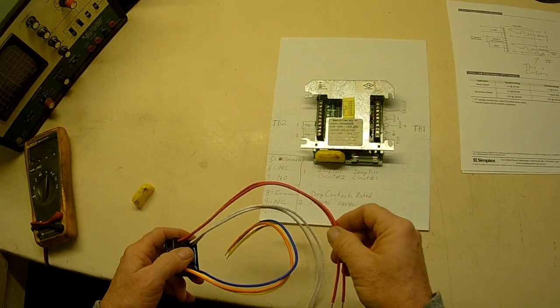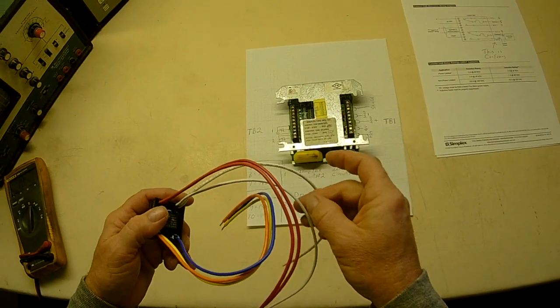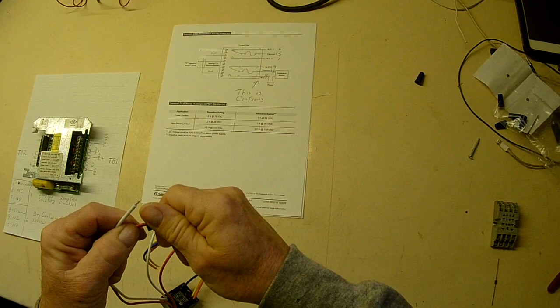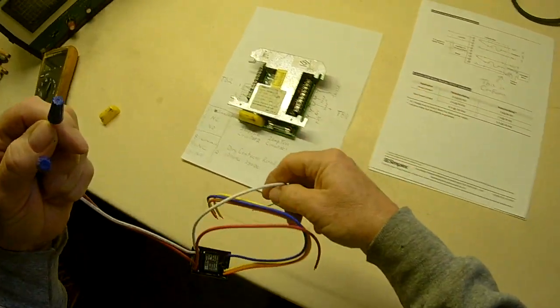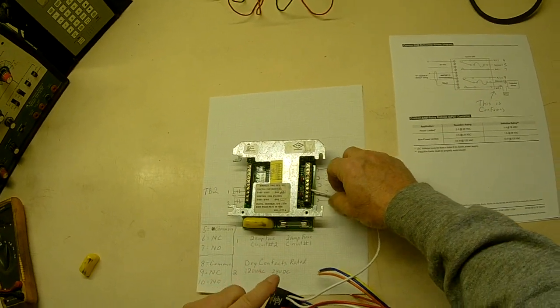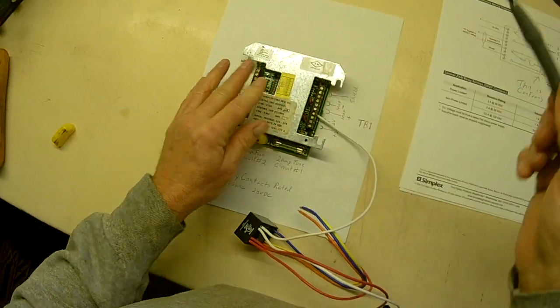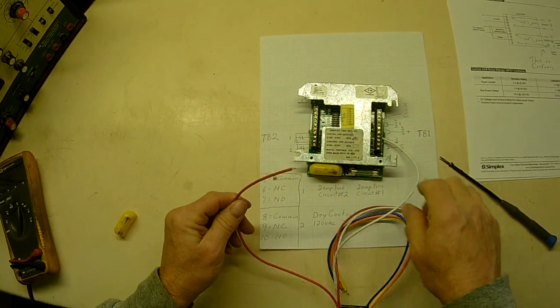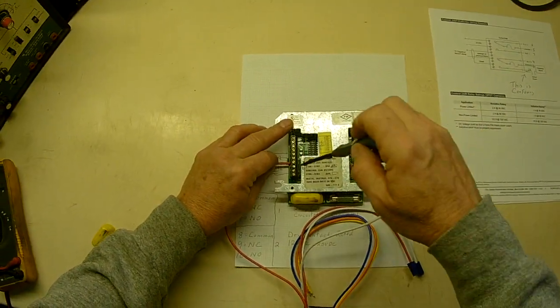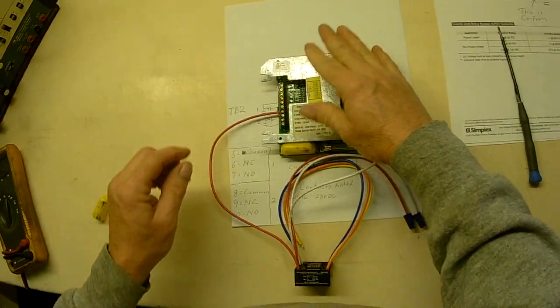So I guess in this situation here, what we're going to do on this is we'll go ahead and take, let's go ahead and take our white wire, one white and red, one red. We're not going to use, we're going to get rid of that. So let's go ahead and say goodbye to a red and white for the time being. White is negative, so we'll go over here to negative and we'll go on zero volts. We're assuming that there's already a negative wire on three. And then we'll go ahead and put that on zero volts. And then our red wire is going to go on, let's go ahead and put it on normally open, which will be seven on the first set of contacts. And the reason we do that is because we just don't want the relay to sit there energized 24/7 unless you're in some type of fail safe application, then you may want to use that.